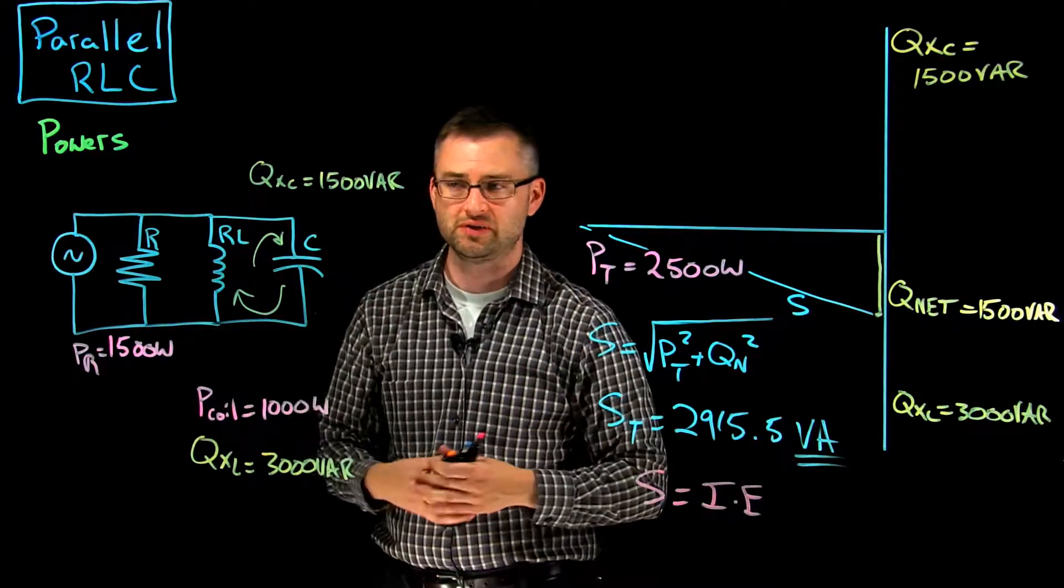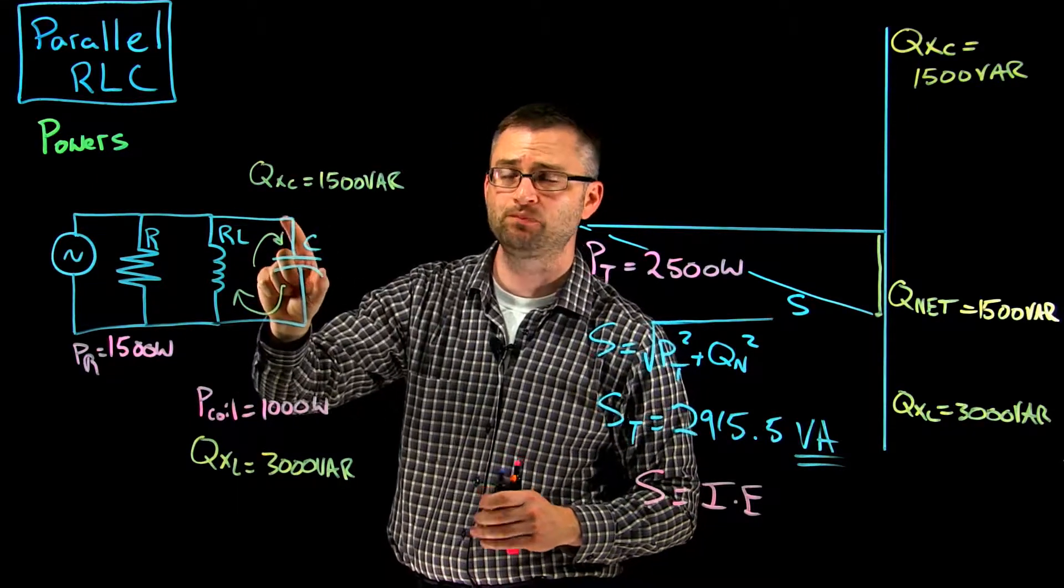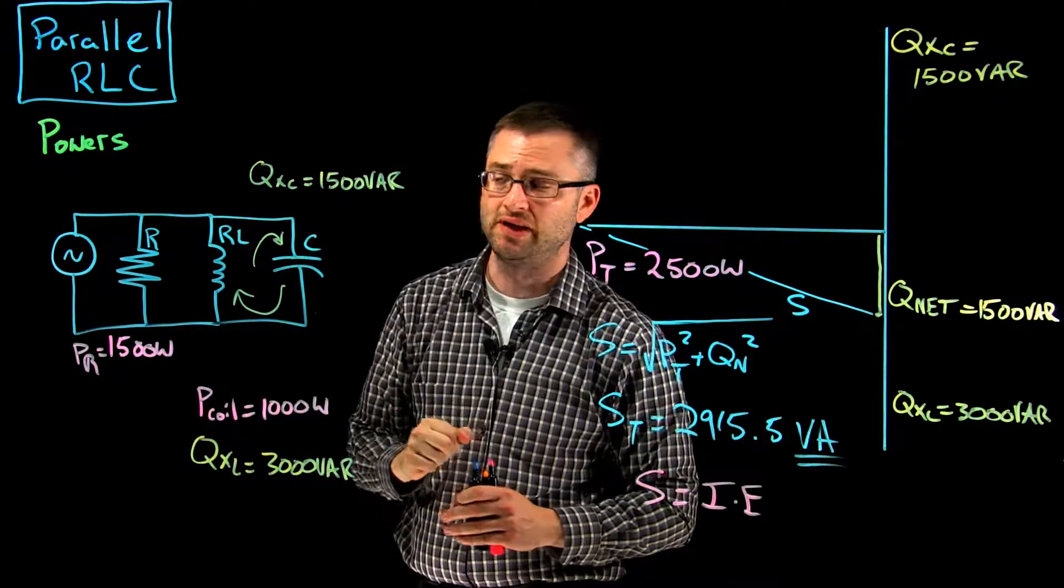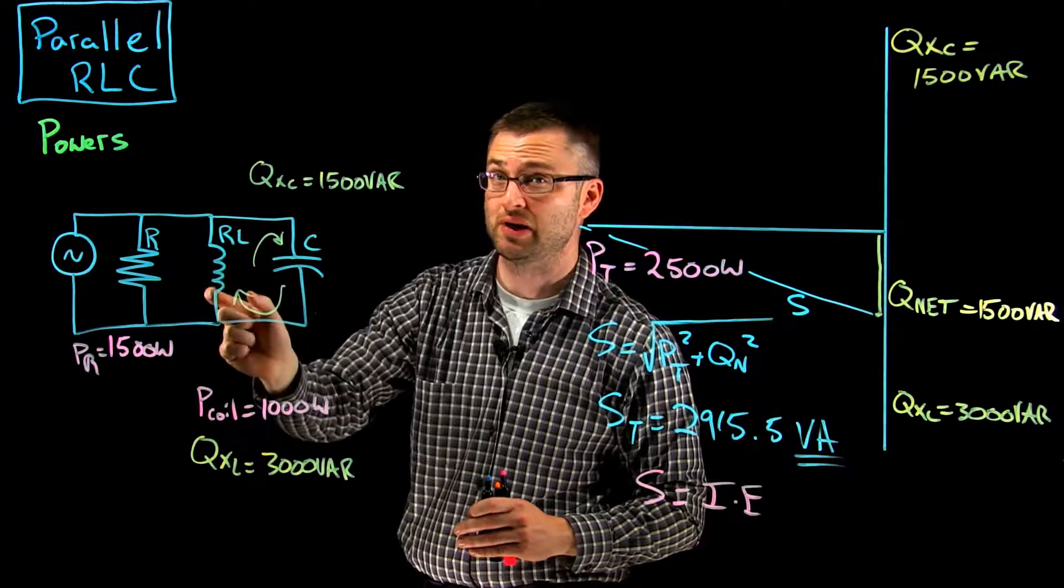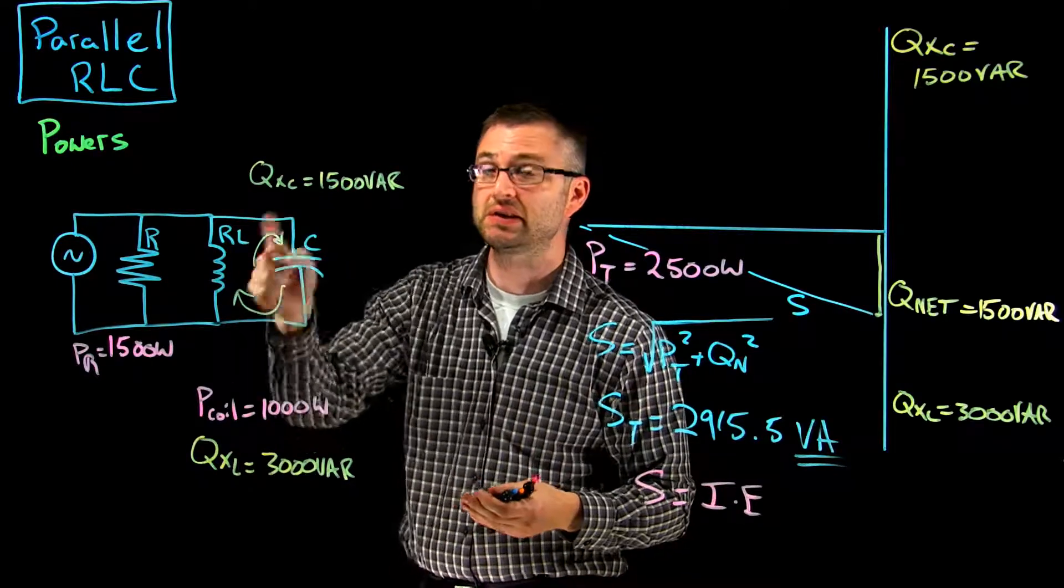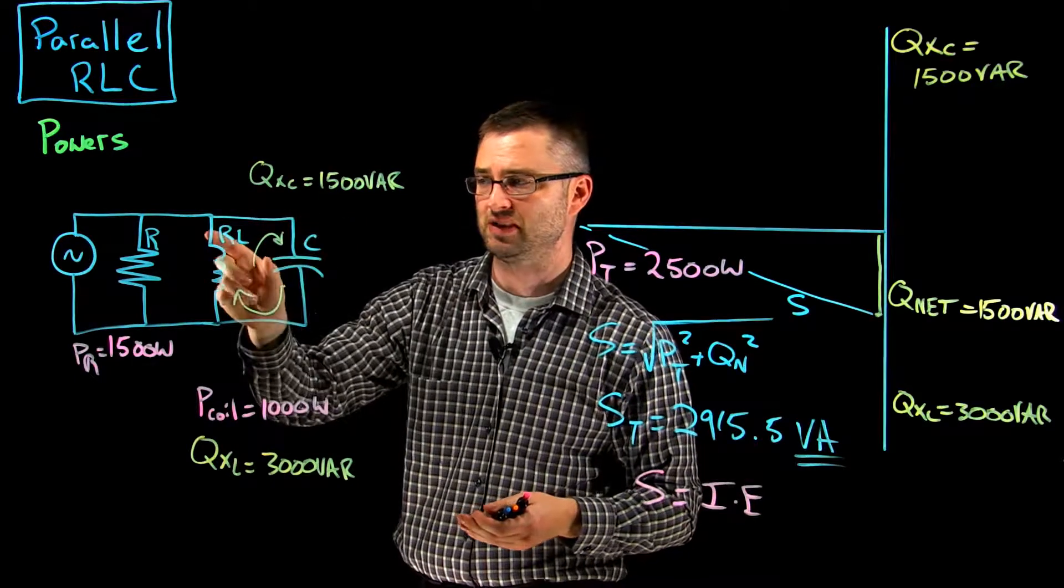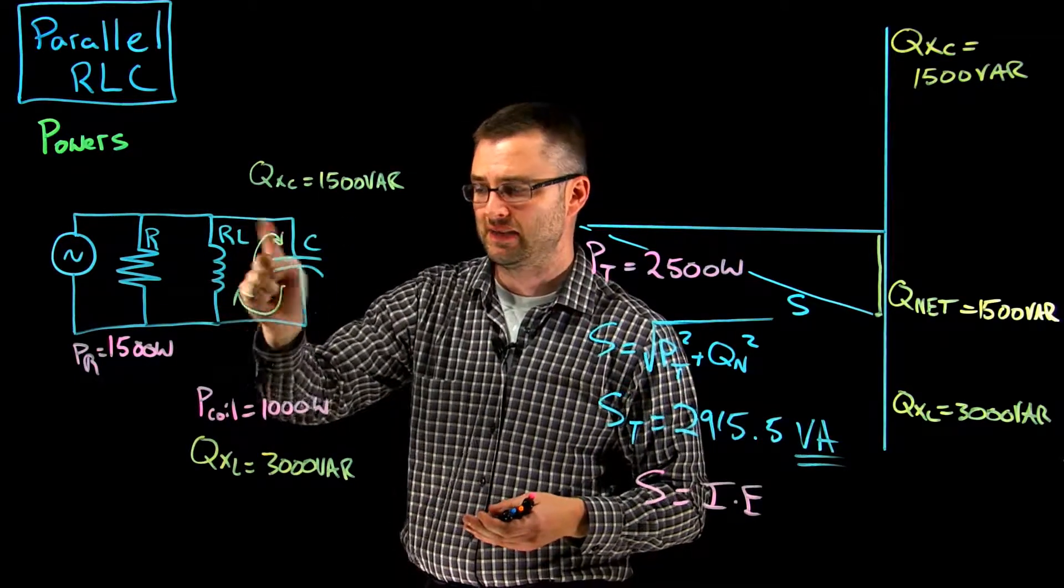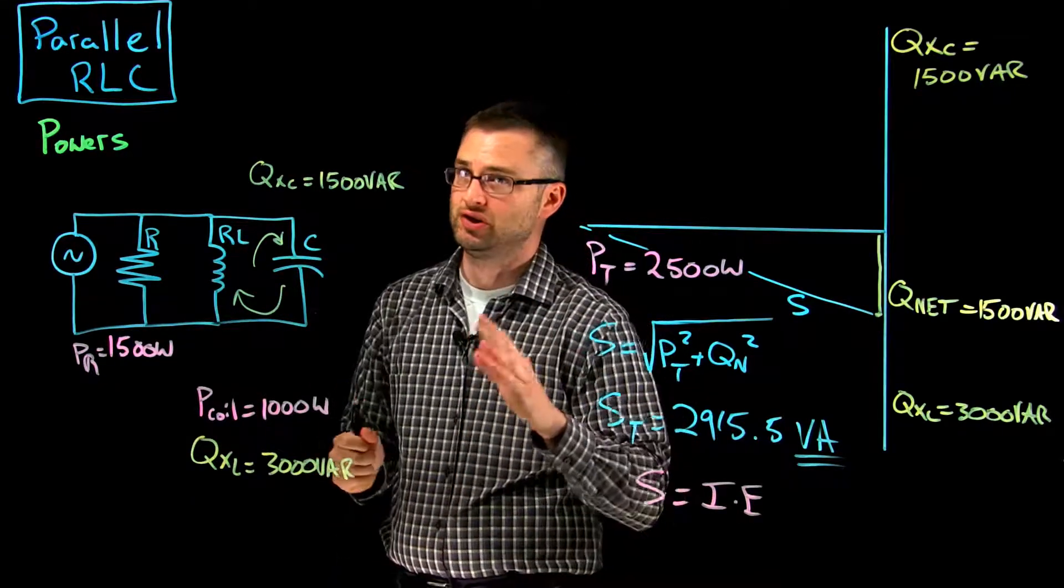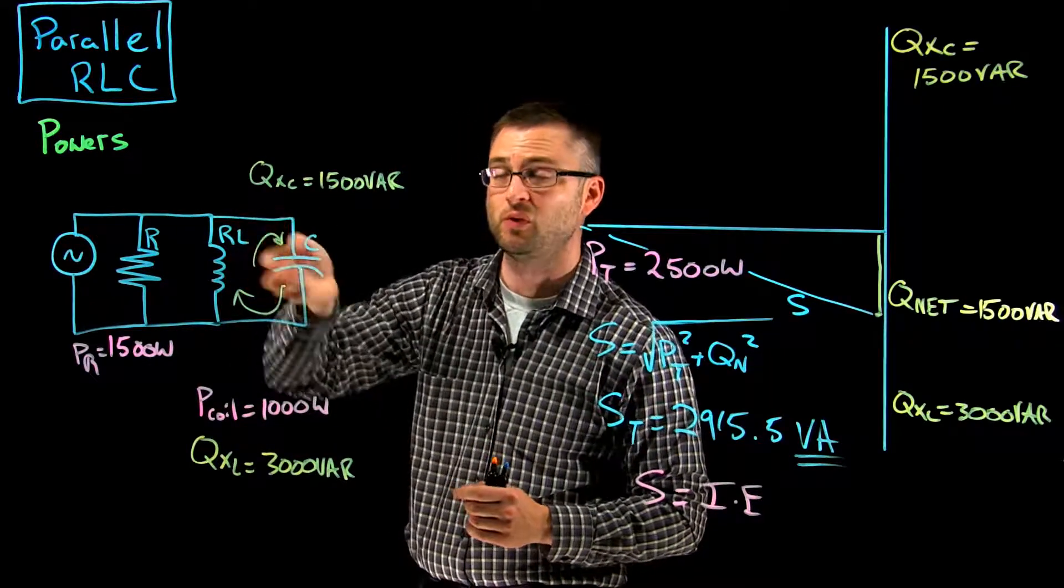But what's important to know is that even though the source isn't providing the full 1500 VArs to this cap, it's still there. There is still 1500 VArs in this branch, and here there are still 3000 VArs in this branch. They don't disappear. The burden is just taken off of the source, and now there's this little circuit inside here as well as the big circuit. So there's a little circuit, and there's 3000 VArs in here and 1500 VArs in here, and those don't disappear. It's just the source no longer has to provide power once this oscillation effect going back and forth starts to happen.